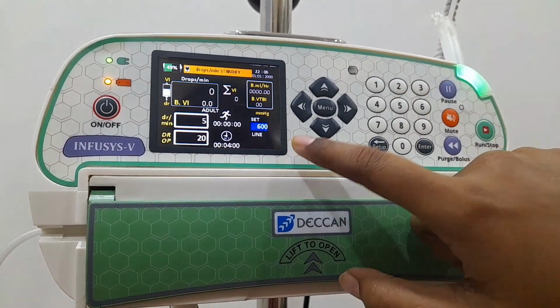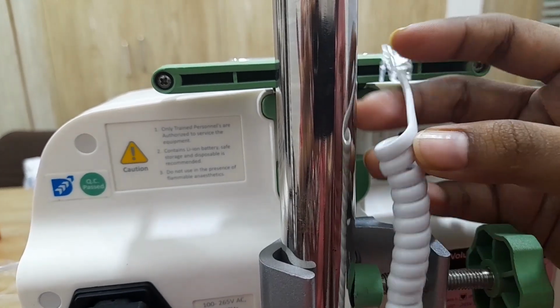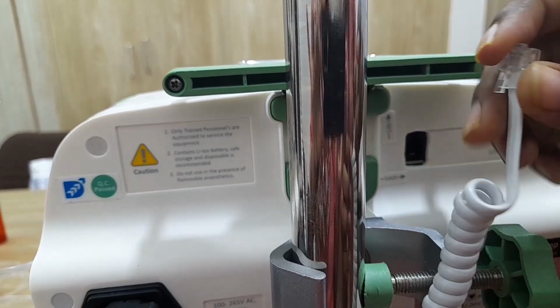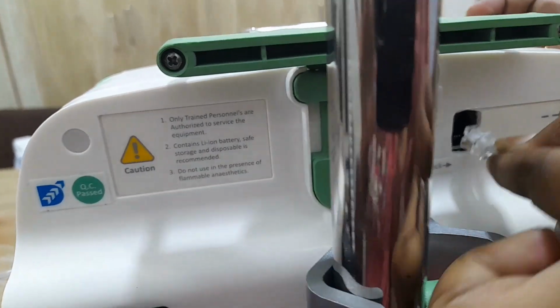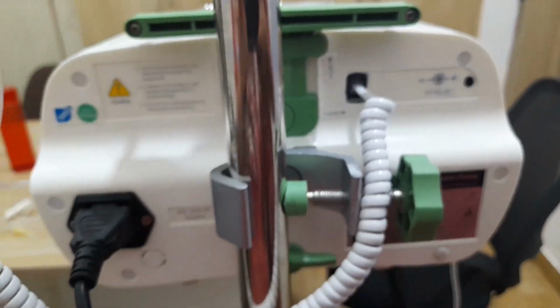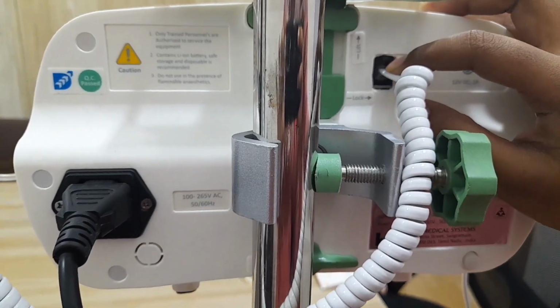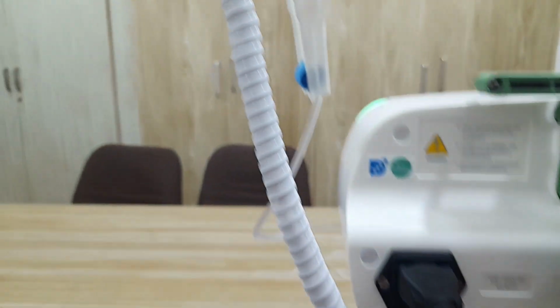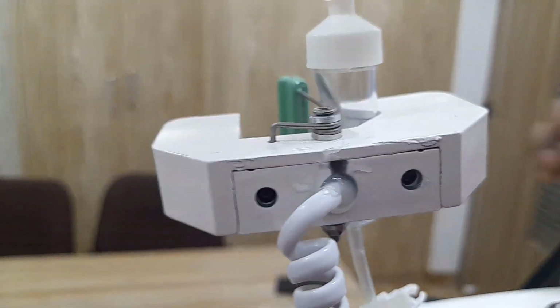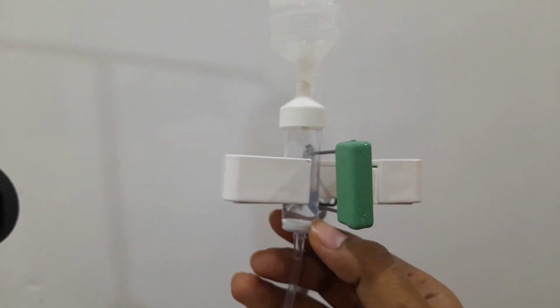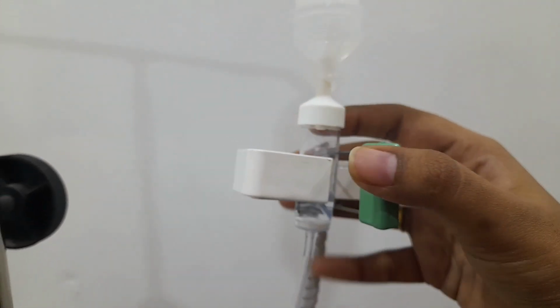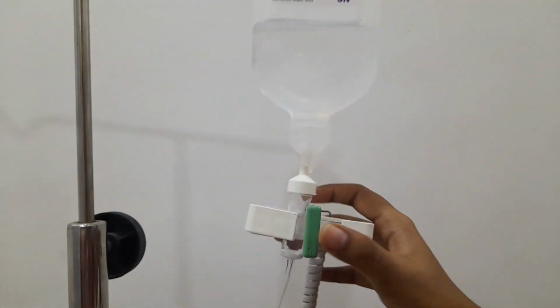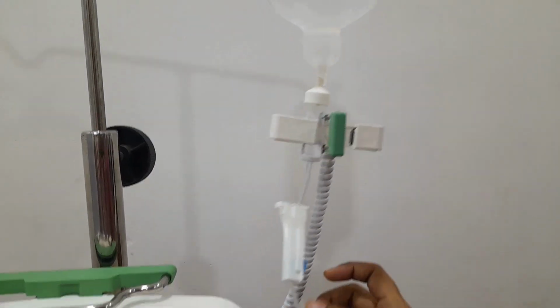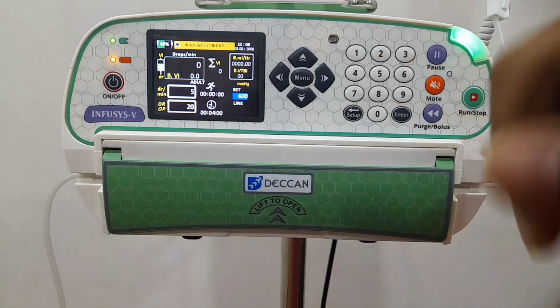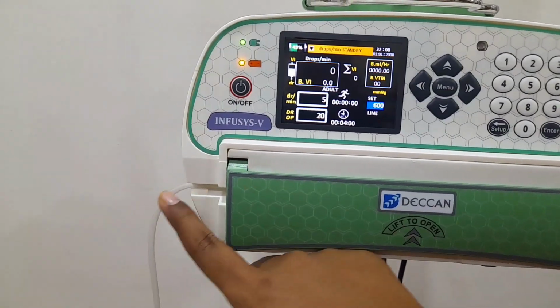In this case we have to use the drop sensor module. So connect the RJ11 connector on the back panel of the unit while using drops ml per hour or drops per minute mode. Connect the RJ11 connector through the provision on the back panel. Then connect the sensor module to the IV chamber. You also have to notice that one third of the chamber has to be filled before starting infusion. Then connect the IV line to the door as mentioned earlier in the video.